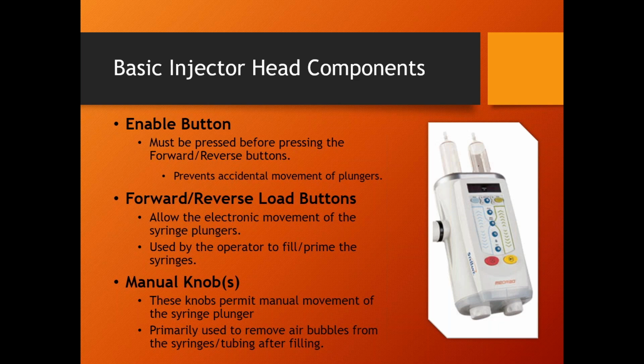But before I hit this button, again, there's a safety feature here. If I hit this button, nothing's going to happen until I hit the enable button, or the arm button, not enable, the arm button. When you hit the arm button, it's called arming the injector. Arming the injector means now when we hit the start switch, we're going to go. You hit the arm button on the head, or you can hit the arm button on the display at either place.